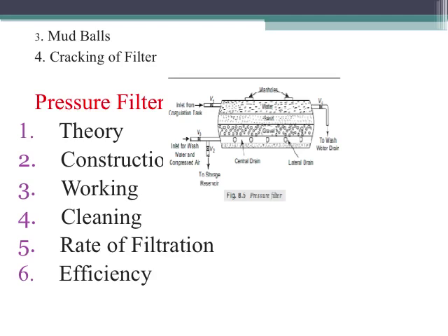With the use of the filter, the loss of head, and therefore the pressure on the sand bed, goes on increasing, which will further start widening the cracks. The floc, mud and other impurities arrested in the filter penetrate deep into the filter through these cracks, thus impairing both the washing of the filter and the efficiency of the filter.